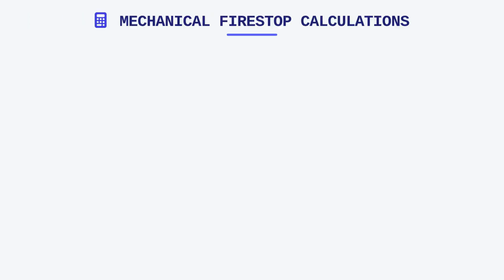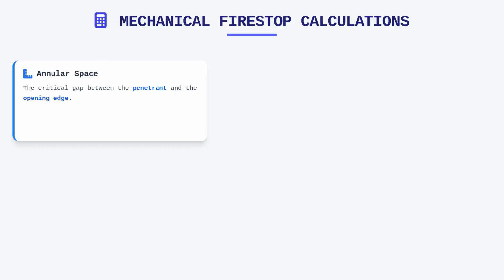Calculating the mechanical aspects of a Firestop installation requires careful attention to detail. We must determine the annular space, which is the gap between the penetrant and the edge of the opening. This space must be wide enough to accommodate the Firestop material, but narrow enough to remain within the tested parameters of the selected UL system.